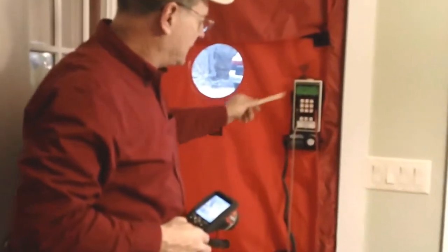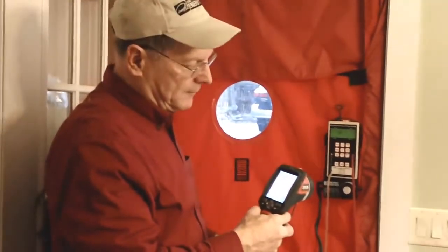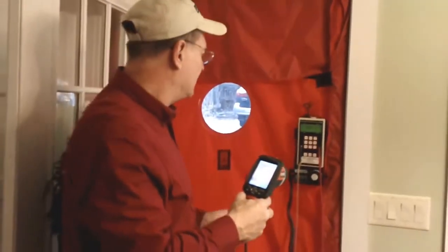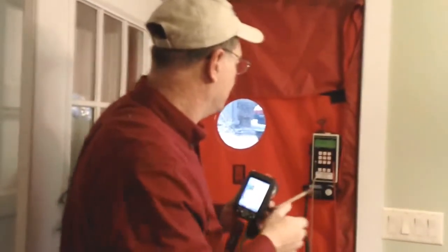We have a blower fan here, which is a calibrated fan for airflow. We also have a calibrated digital pressure gauge to tell us what the actual flow rate is. There's a test pressure we set the instrument at, and again we have an infrared camera here which we'll also use to take a look at where the air leakage might be coming in. This particular house is a very old home, but there's been some improvements made, and we want to see where the insulation levels and where the thermal qualities are at of the stuff that was retrofitted.